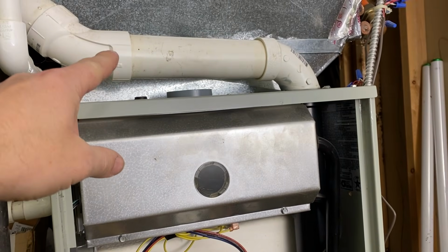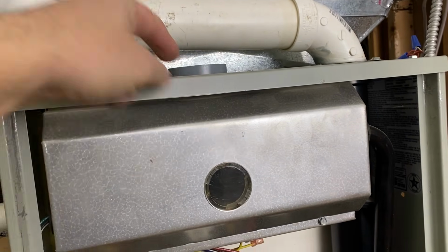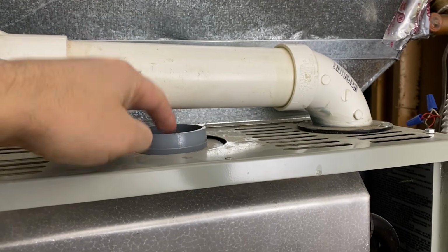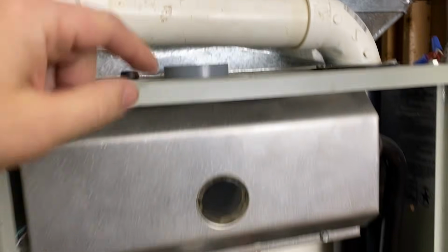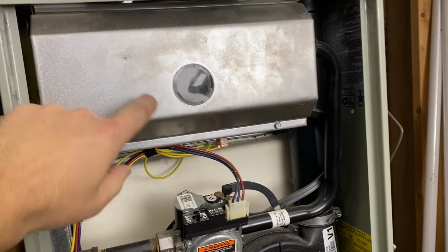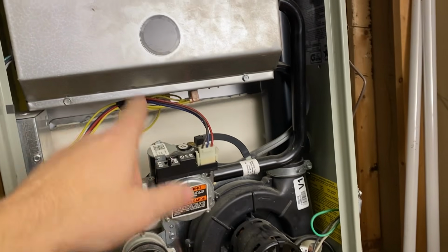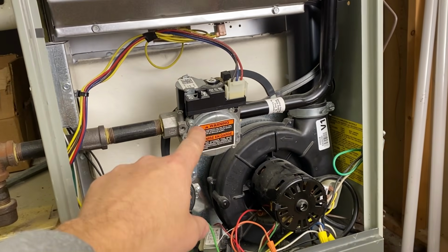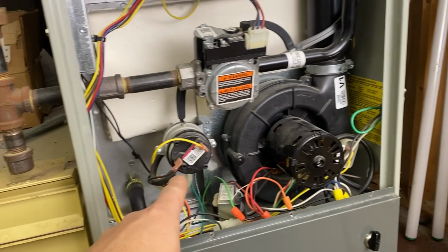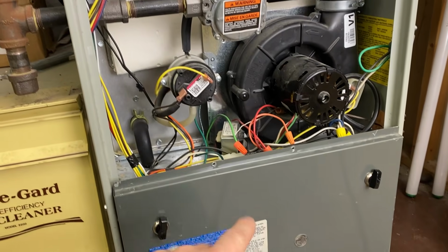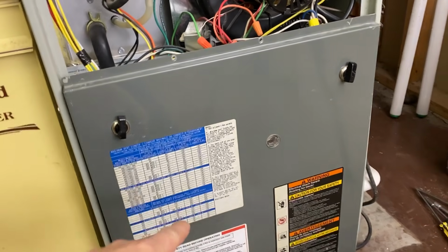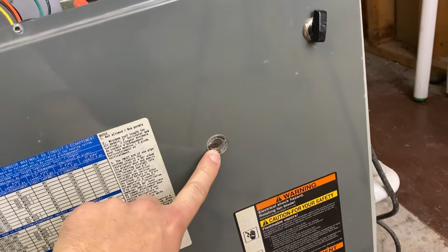So we have our PVC vent here. This one actually has an open intake, so it intakes fresh air and comes into the burn chamber from the room. This is our burn chamber here. This is where the burners are, and there are a couple of sensors and things like that we'll talk about. We've got our gas valve, our induced draft motor, and our pressure switch here. Down below is the actual blower. Now in this one, there's a little sight hole right here.